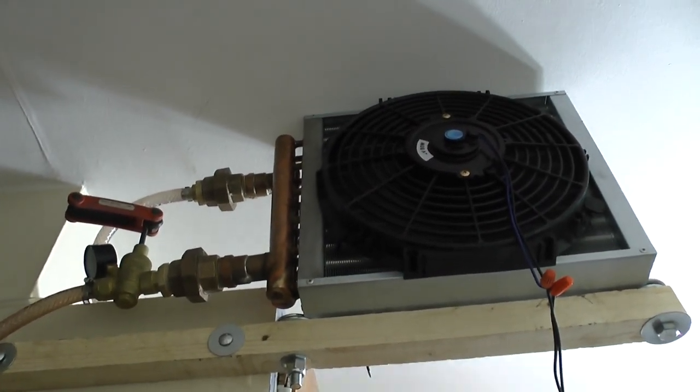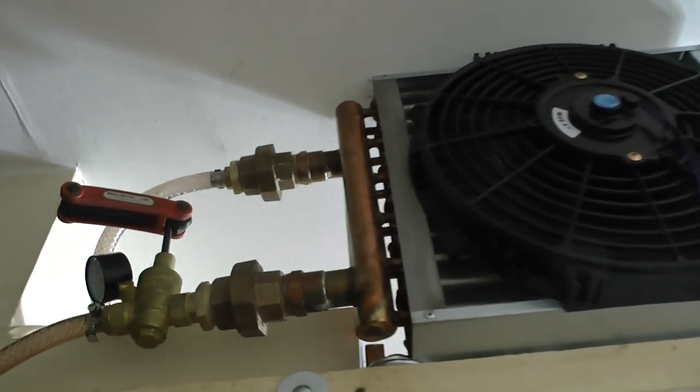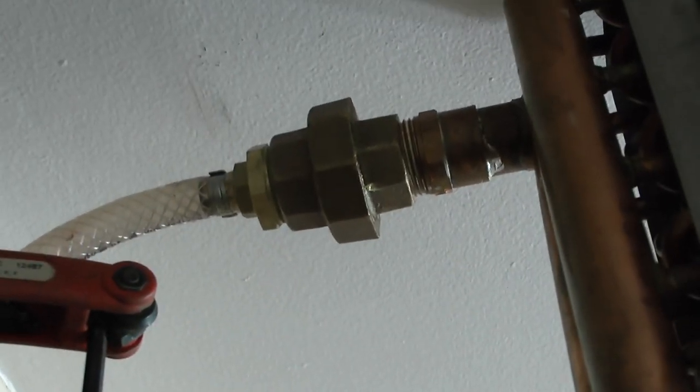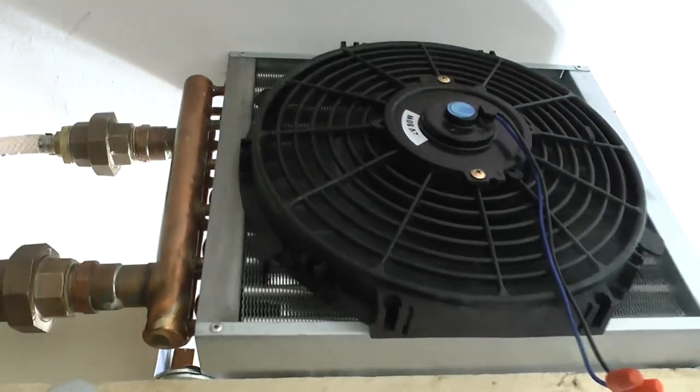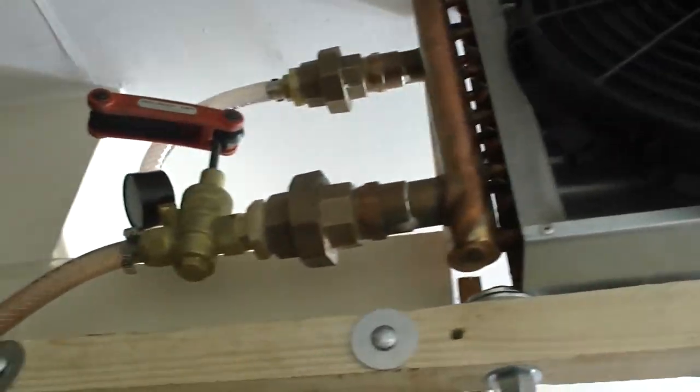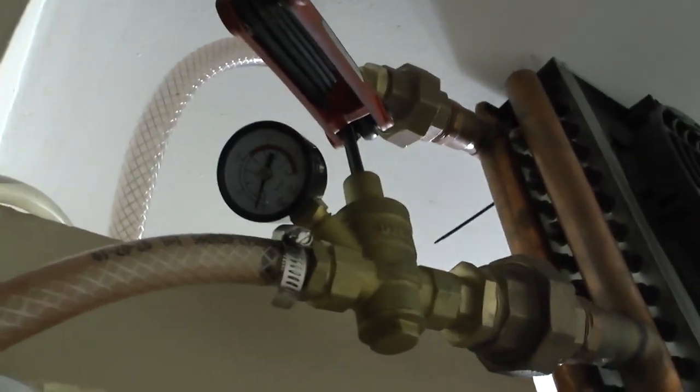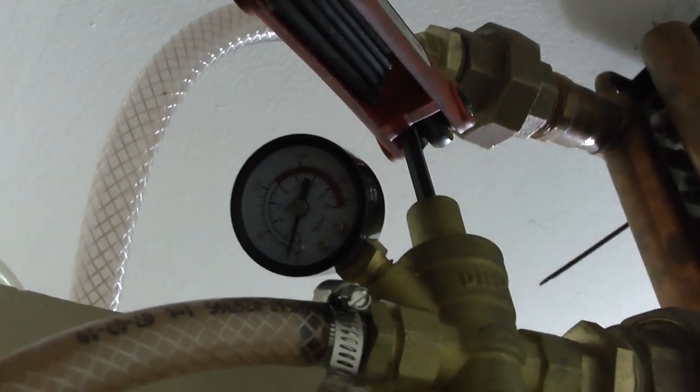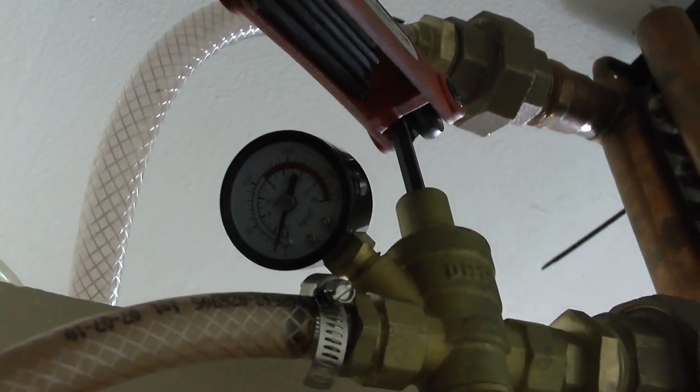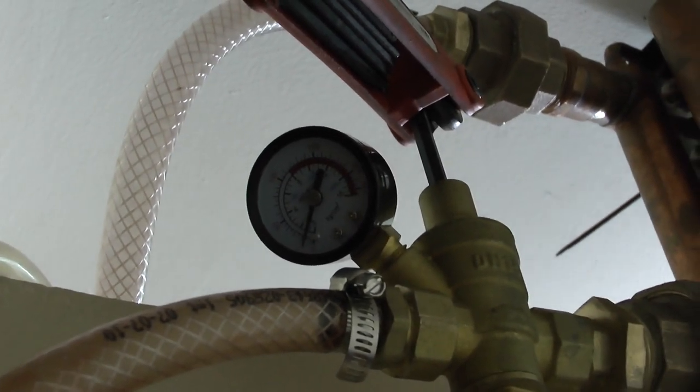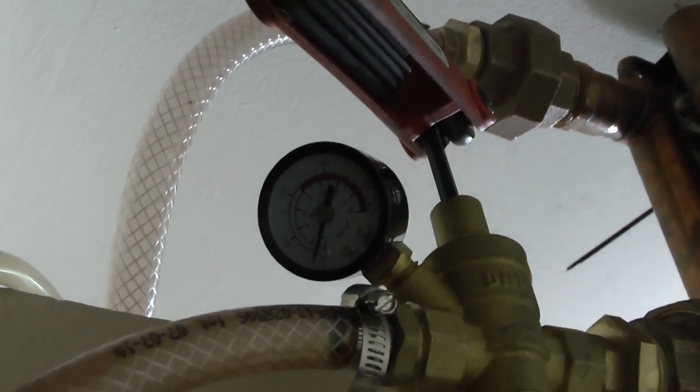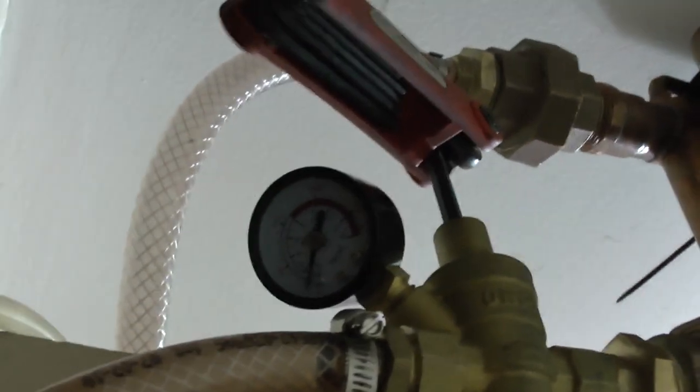The radiator is actually not doing much. If we go up here and I zoom in, that is the input line going into the coils going out to a pressure reducing valve, and right now I think if we can see it, it's got about five psi or so in there. I've got really shaky hands so it's hard to keep stable, but I can turn that up if I can't get up there and shoot at the same time.